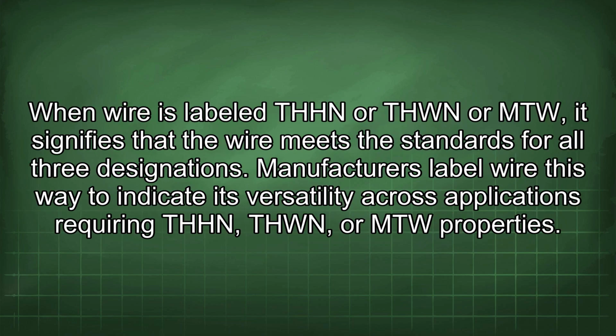When wire is labeled THHN or THWN or MTW, it signifies that the wire meets the standards for all three designations. Manufacturers label wire this way to indicate its versatility across applications requiring THHN, THWN, or MTW properties.